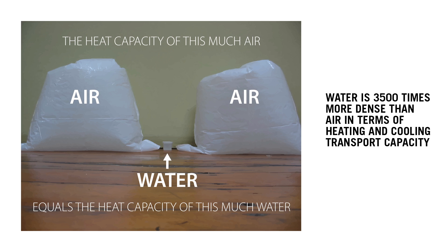We didn't talk about chilled beams, and this picture here is why we do chilled beams. Basically the heat capacity of those two bags of air can be carried by this thimbleful of water, so you move a lot more heat in a smaller volume for cooling.